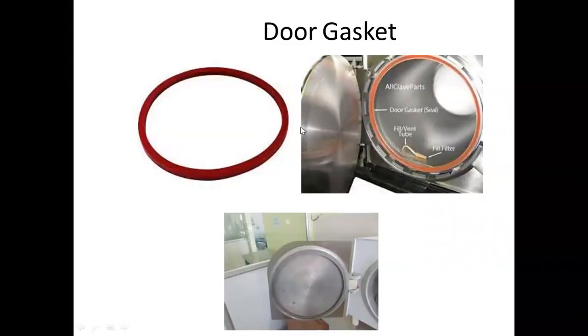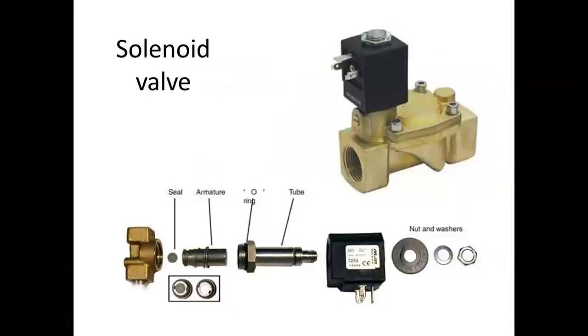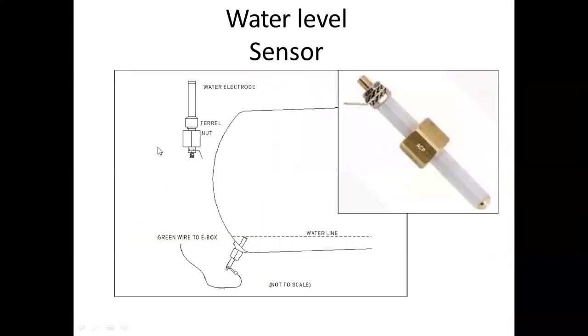So this is the gasket which is present, which is covered over the autoclave machines. After that, the door will be locked. This is door gasket. The next, solenoid valve. This is the solenoid valve which is used for the valve which is connected with the nut and washers. Okay, this valve is present. The next, water level sensor. With the help of this, the water electrode will be able to sense what the water level is. If water level is not sufficient, it can able to give us the signal.